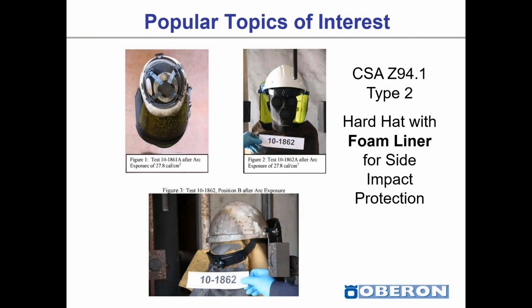And here we have just a common example of one of the frequently asked questions I get, such as the type 2 hard hat. So in Canada, we have two different types, type 1 and type 2. Some of the provinces require by law that you wear a type 2 hard hat. You determine the type of hard hat based on the risk or the severity, so the potential injury to the worker. Many employers have determined that a type 2 is necessary based on the potential flying debris created by an arc flash. And that foam liner in a type 2 provides that side impact protection.